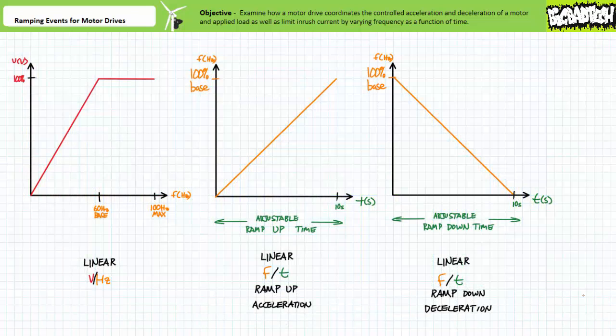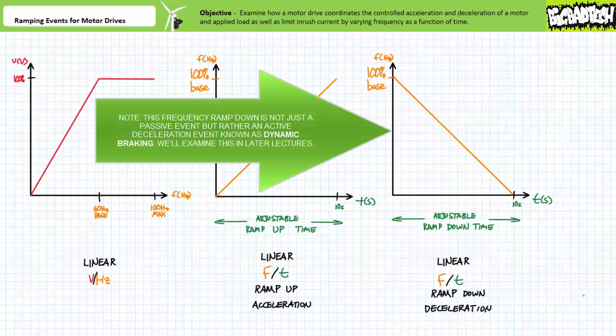The ramping of applied voltage and frequency is not exclusive to soft starts but can also be used to soft stop a motor with a driven load for the purposes of controlled deceleration. In what is almost a mirror image of our previous example, consider a motor drive with a simple linear volts per hertz profile, a linear acceleration ramp-up profile, and another plot where excitation frequency is ramped down from base frequency to zero over an adjustable deceleration ramp-down time of, let's say, 10 seconds. Given a running motor at full voltage and full speed, a stop command would initiate the deceleration ramp-down event. This means while excitation frequency is ramped from 60 hertz down to zero hertz over 10 seconds, voltage is also ramped down from 100% to 0% over the same 10-second period. At five seconds into the ramp-down event, excitation frequency would be 30 hertz and applied voltage would be 50%. When the ramp-down event finishes at 10 seconds, both excitation frequency and applied voltage reach zero, and the motor and driven load glide to a controlled stop.